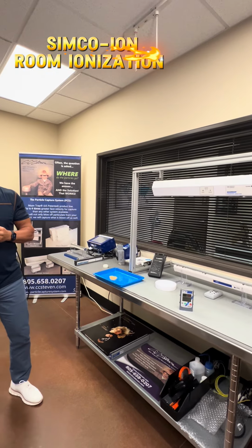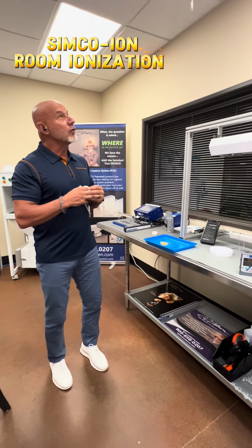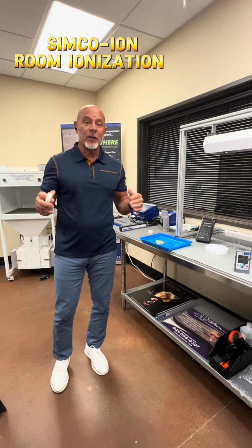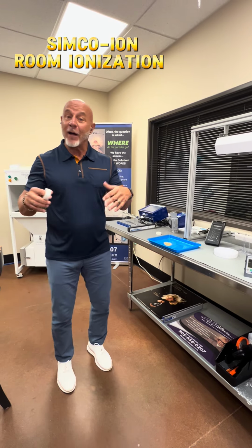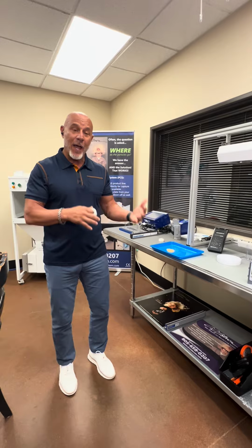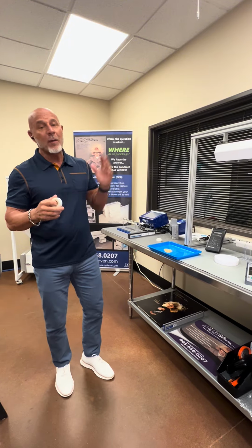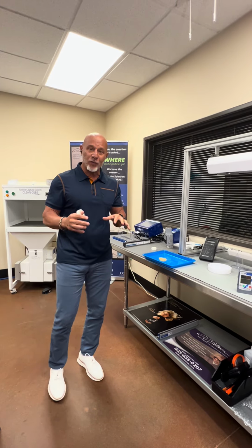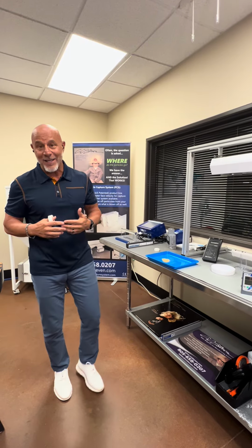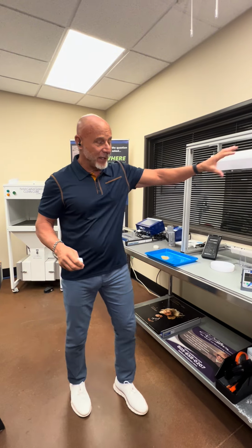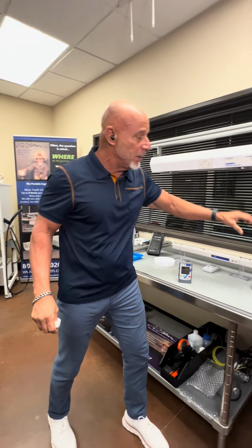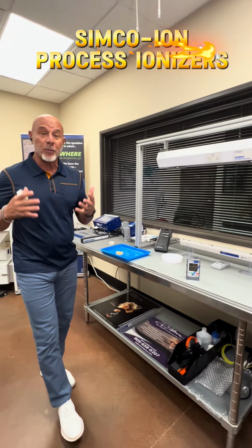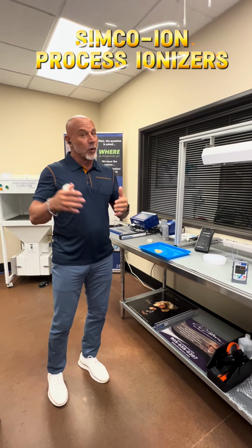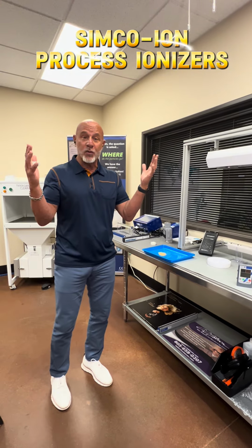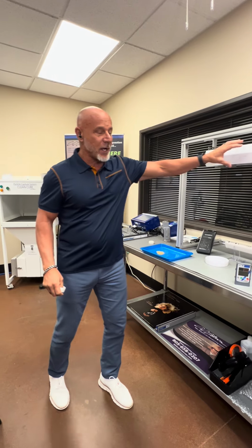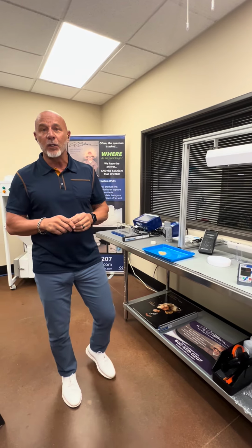When I think of room ionization, I want to give you this analogy. Room ionizers are like the sprinkler systems we see in every building. They're designed for suppression, to keep fires down and keep anything that might have happened suppressed to a safe level. That's the same with room ionization. They are designed to suppress fields so that they do not get high enough to cause that ESA, that electrostatic attraction. Process ionizers, I want you to think of them as a fire hose. So when that fire does present itself, either in a critical work process or a tool or a cell that's not exposed to that room ionization system, process ionizers are great to mitigate, eliminate that field immediately.